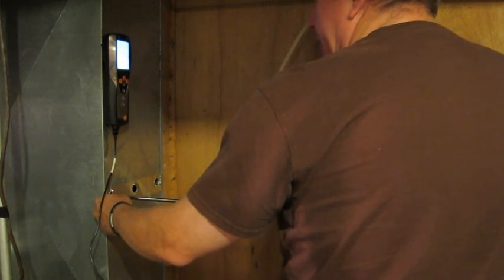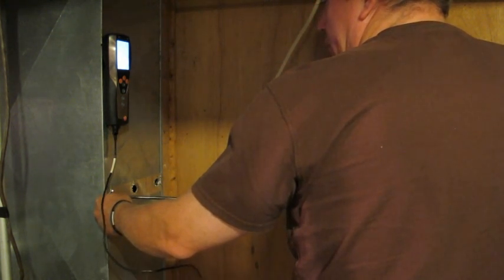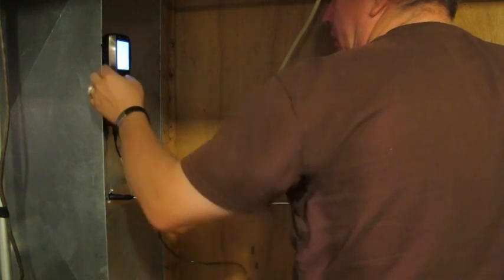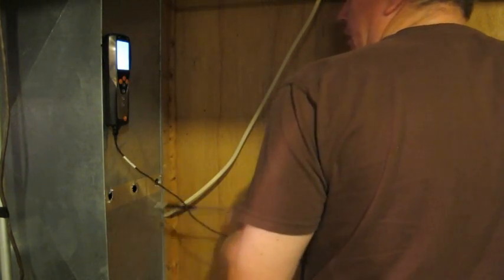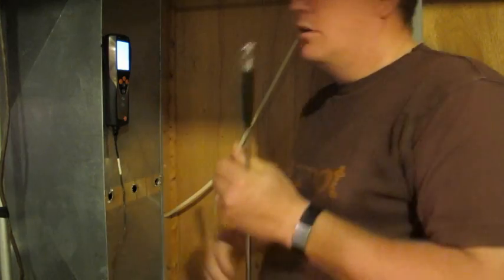This is going to take a time average, and it's going to give me my average CFM and my average BTU. Right now I'm operating at about 34,500 BTU, right at 1,200 CFM. So let's go outside and I'll show you the second part of this.